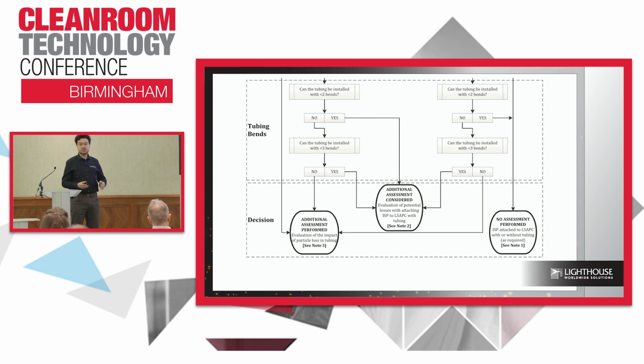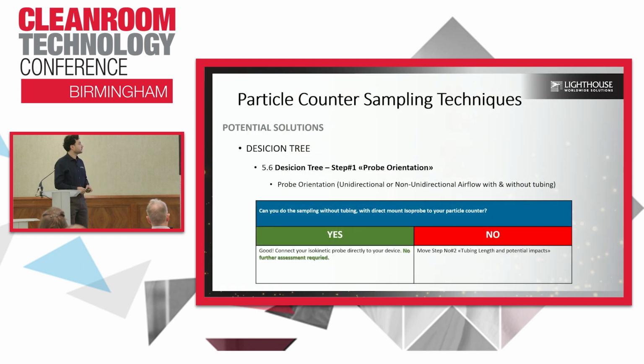So this is the decision tree. This is not a magical thing, but it's good to start with. Let's take a look at how we will use it. For example, the probe orientation: you will go with step number 1, how you will be placing your probe. Okay, can you do the sampling without tubing, with the isoprobe mounted directly to your particle counter? If you say yes, you're done. No other evaluation is necessary for your system. But if you say no, then okay, define the tube length, and we will tell you the potential impact.